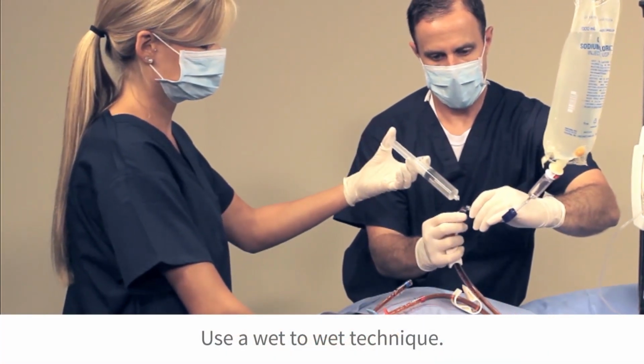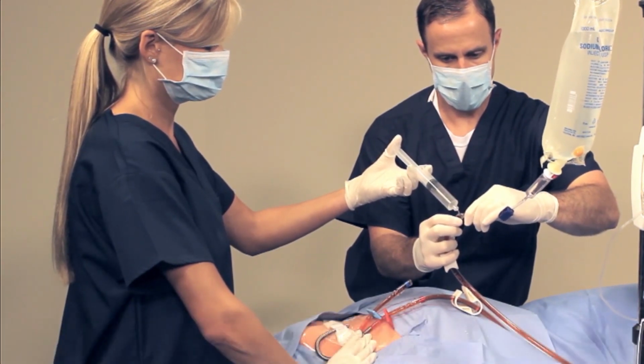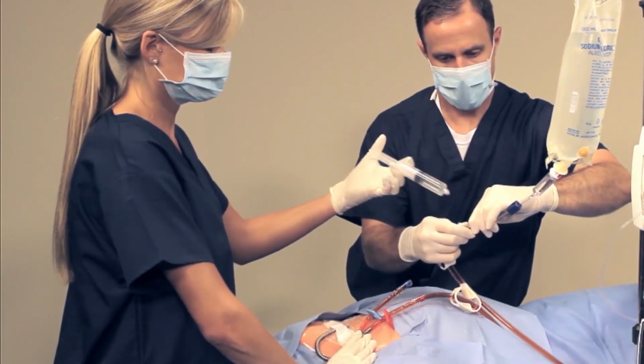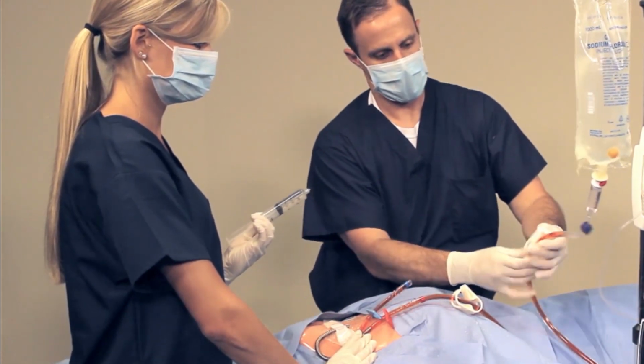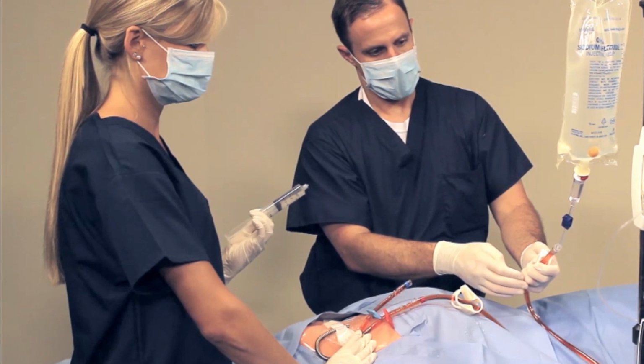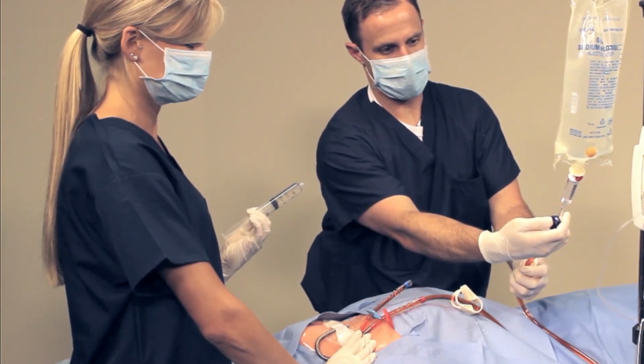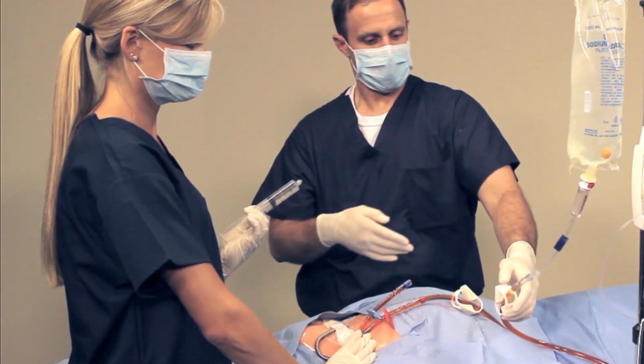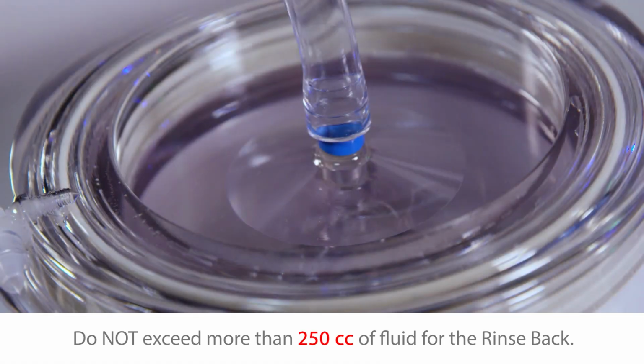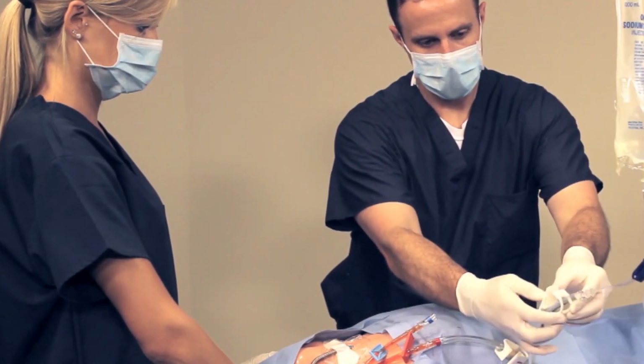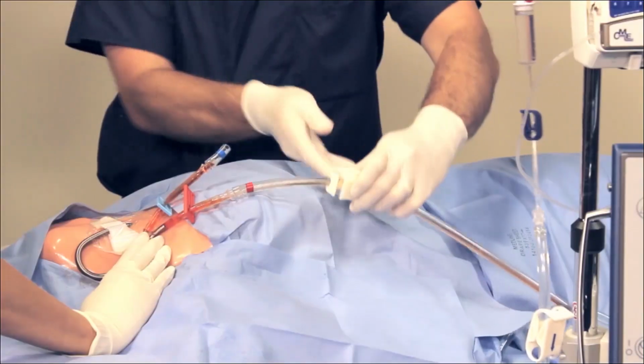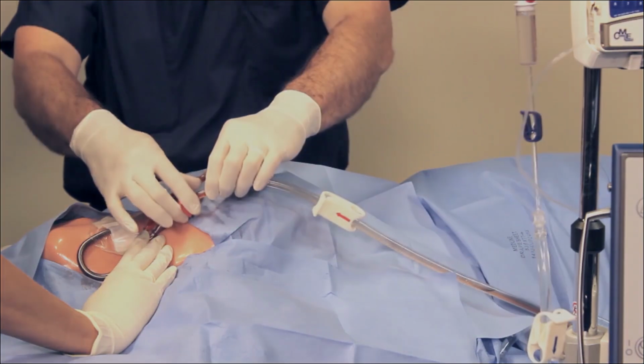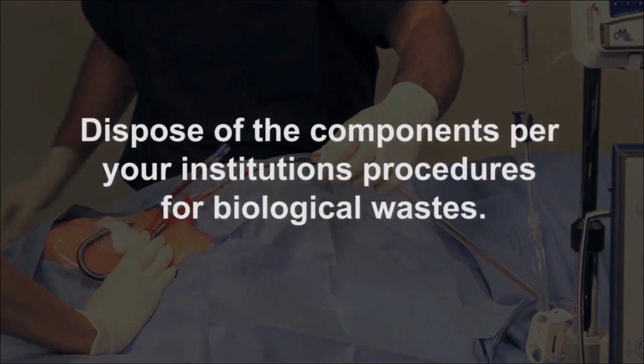Using a 30 milliliter saline-filled syringe, provide irrigation for the connection of the priming spike barb connector and the blue tubing. Ensure there is no air trapped in the tube. Open the clamp on the blue tube and the blue clamp on the priming spike barb connector. Saline will begin to flow by gravity through the cartridge, rinsing the blood back to the patient. Once the blood is returned, close the clamp on the blue tube and the priming spike barb connector. Clamp the red tubing. Remove the catheter using standard clinical procedures for removing large-bore central venous catheters.